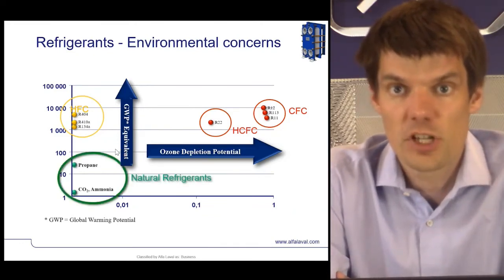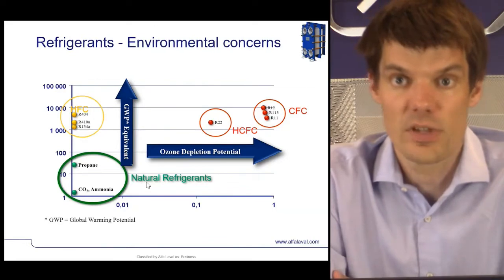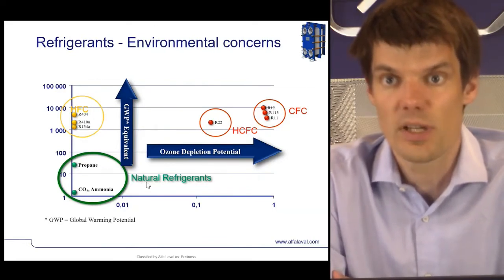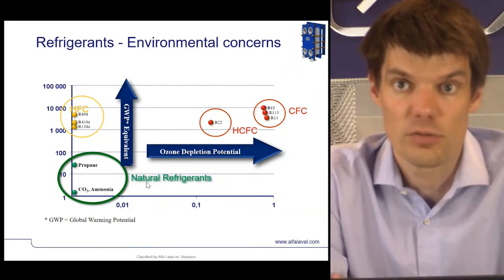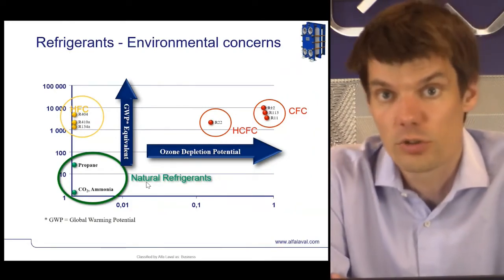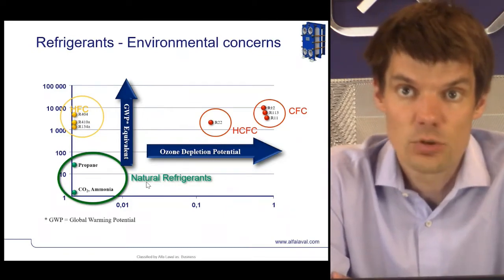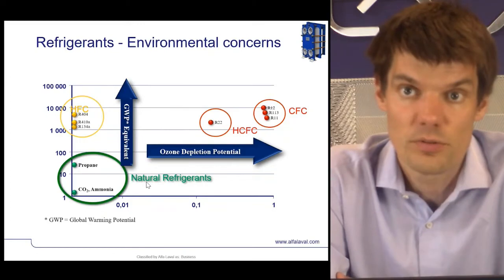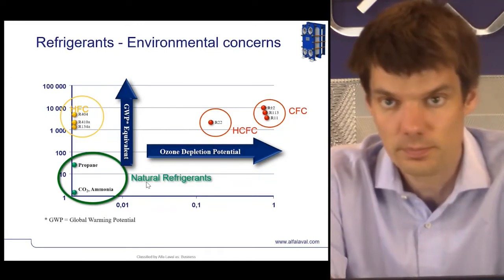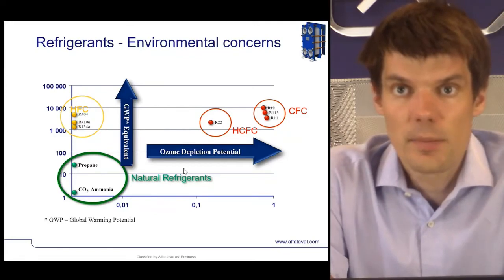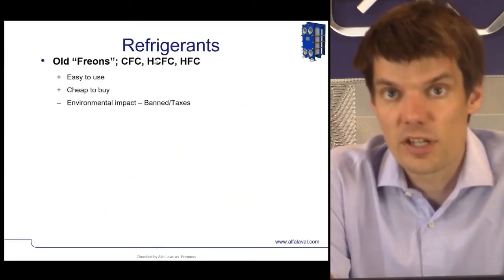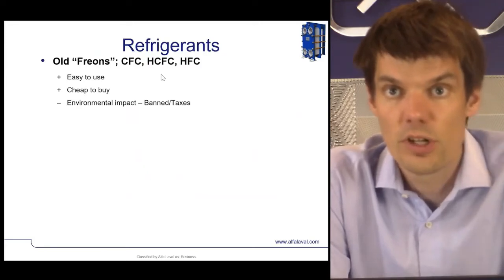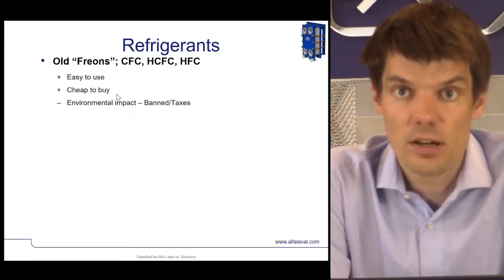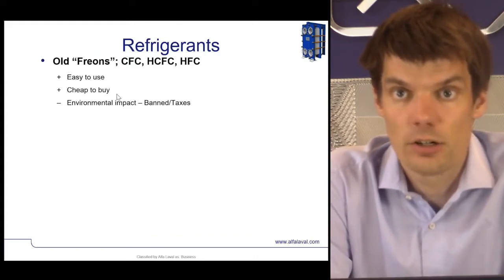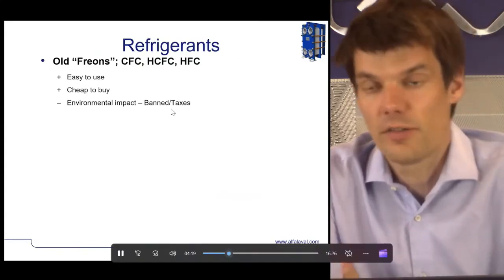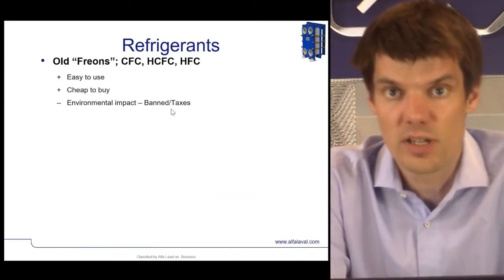The natural choice would possibly be to change to a natural refrigerant. That is things that you can find in nature, like CO2 and ammonia, as these are very efficient refrigerants with no global warming potential or ozone depletion. However, these have some drawbacks, which has resulted in the new refrigerants, so-called HFOs. If we sum up the situation, we can conclude that the old freons such as R134A, R22, R404 are relatively easy to use. They are relatively cheap to buy, but unfortunately they are not good at all for the environment. Therefore, they are effectively being banned or taxed out in most markets today.